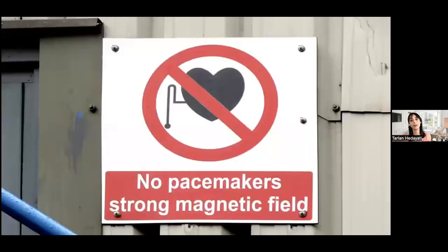Now, the most common cause of failure to pace is oversensing. And a way to think about oversensing is that the pacemaker gets overwhelmed by other signals.